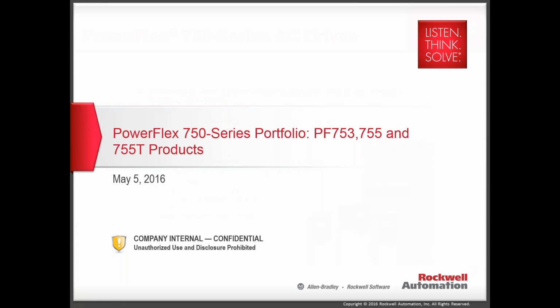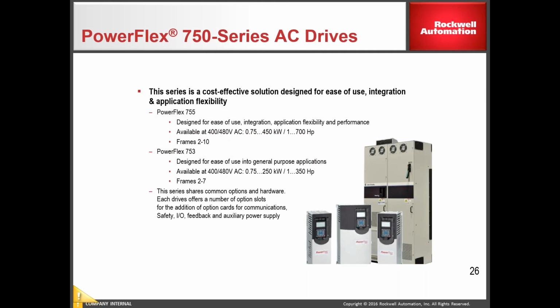So PowerFlex 750 series products. We've got the PowerFlex 753, the 755, and we've got a new product coming out called the 755T. So we're going to step back a little bit. With the 750 series, the 753 and the 755 are the 2 drives that we offer today. All right, and the 753 goes up to 350 horsepower. That is a wall mount drive. Okay, frames 2 through 7. So when you go above 350 horsepower, it becomes a floor mount drive. So the 753 doesn't go any higher than 350. Above that is the 755, right? And we can go all the way up to 2,000 horsepower with the current offering today.